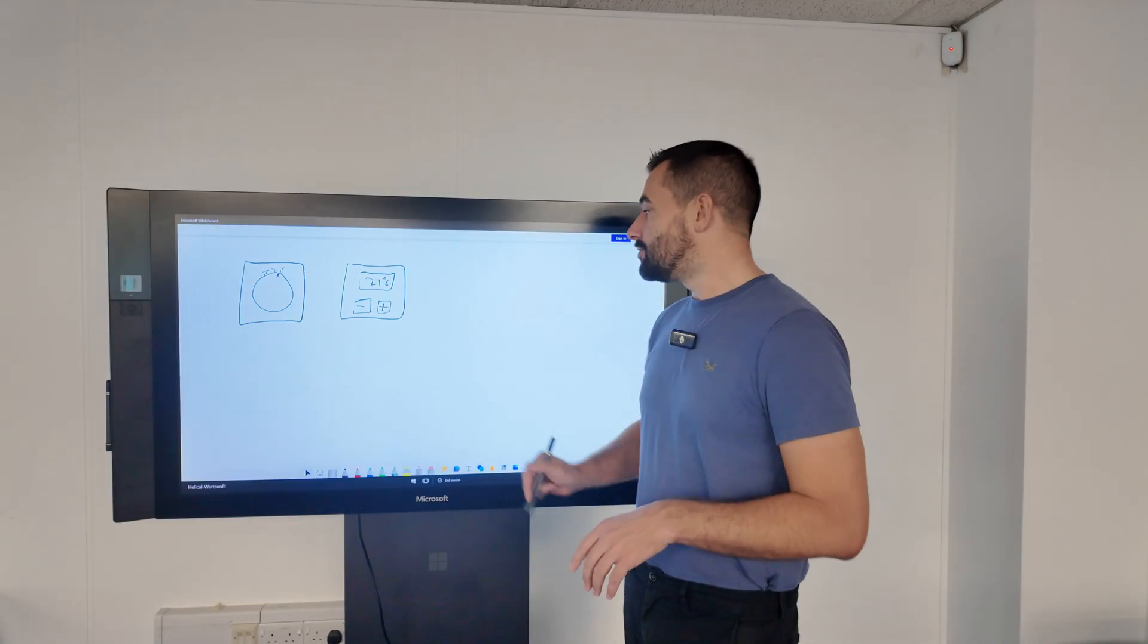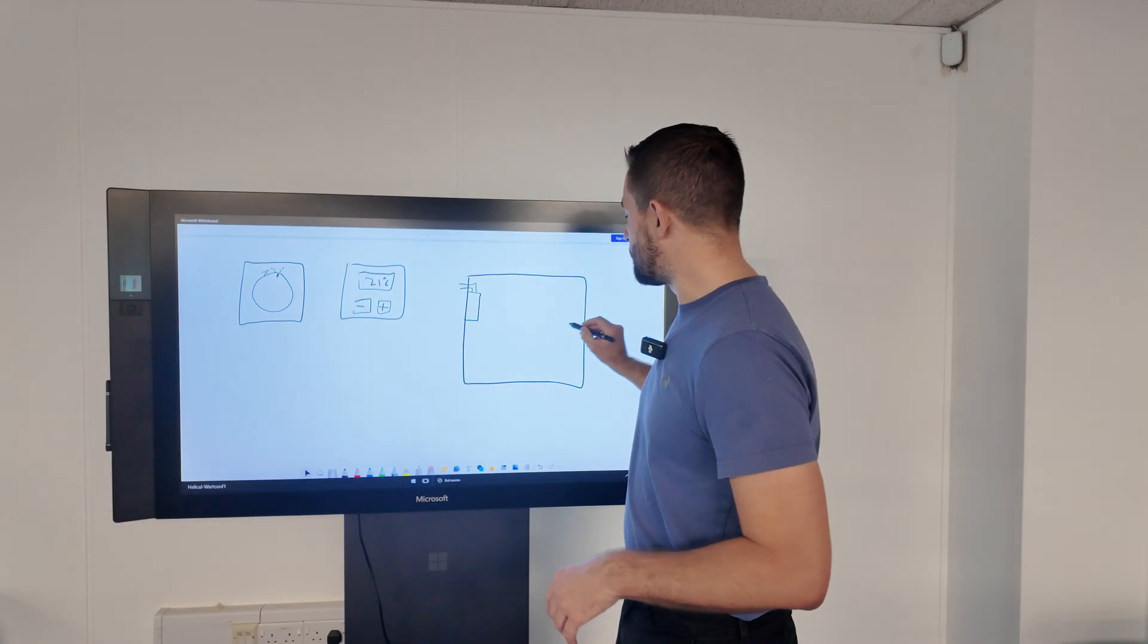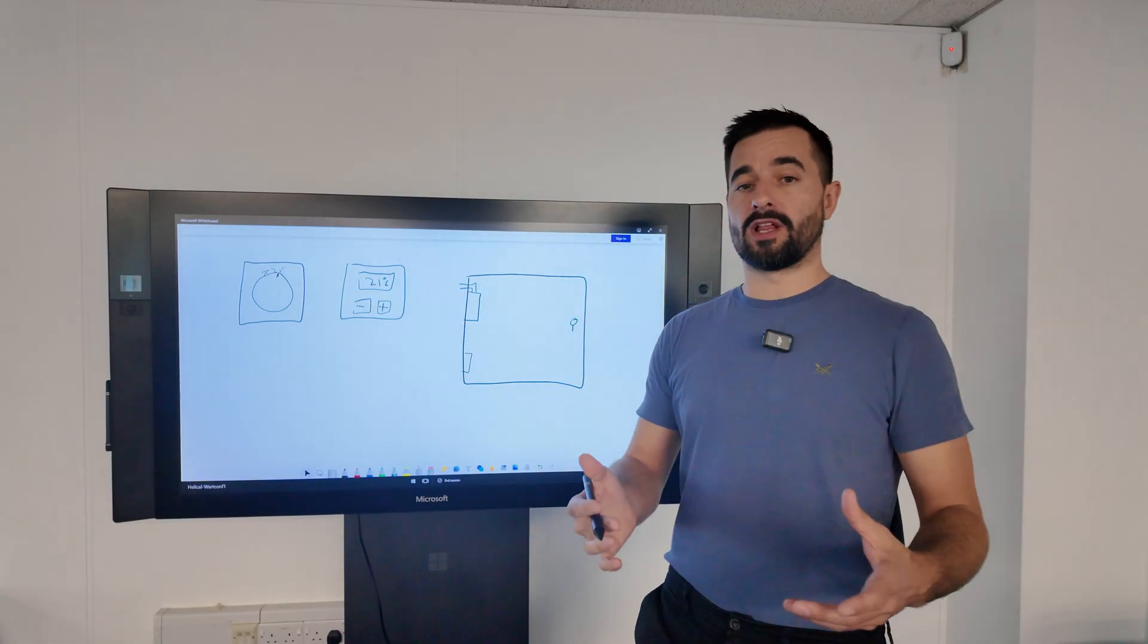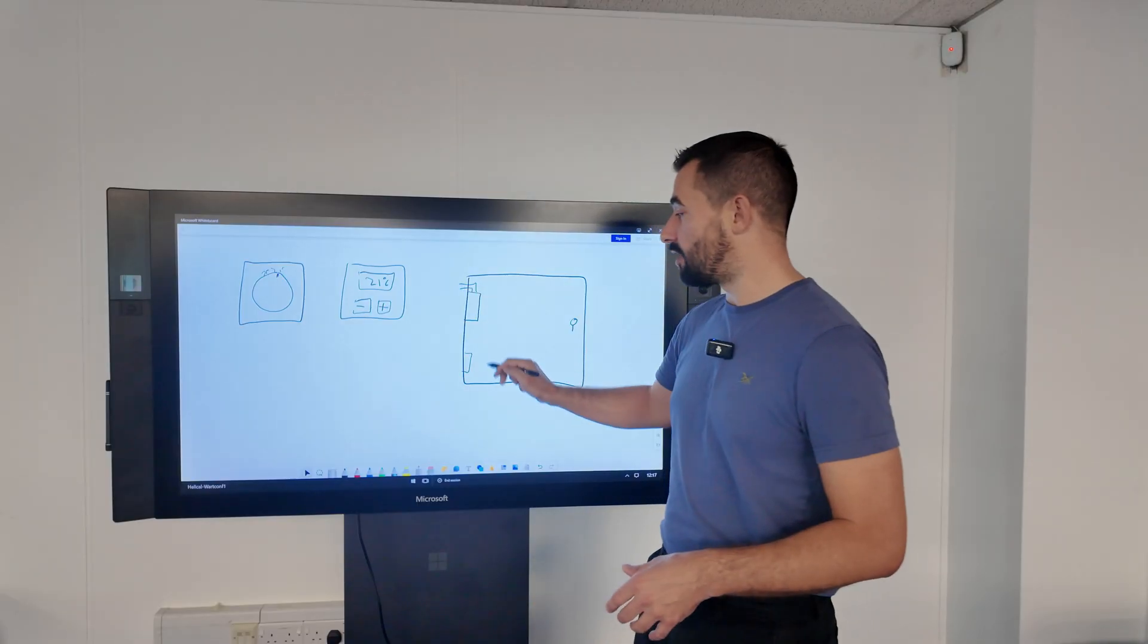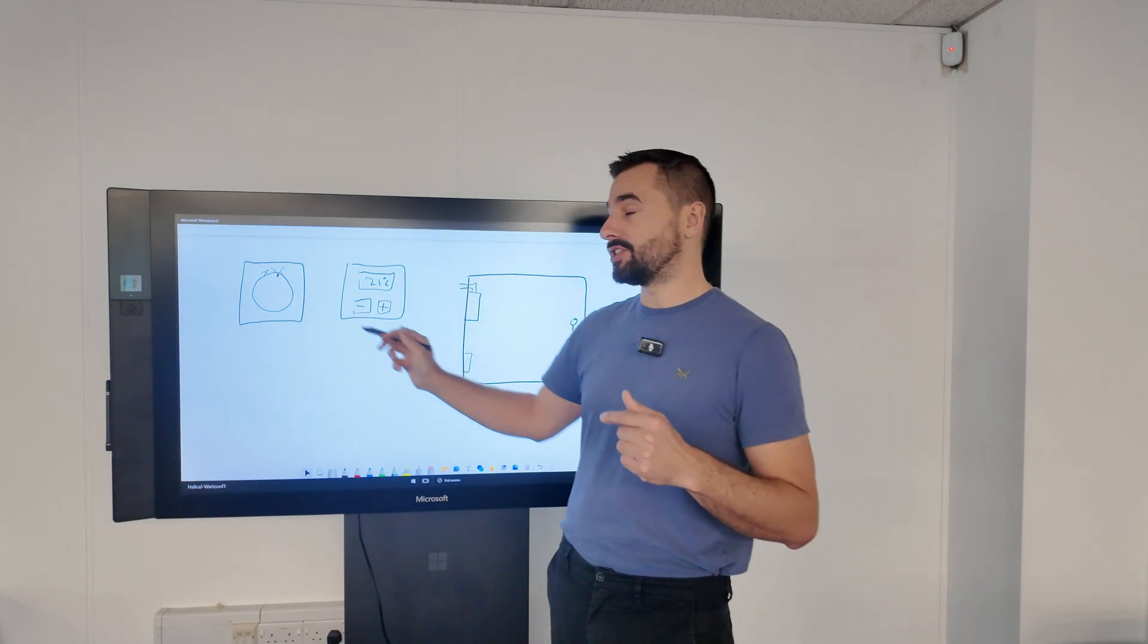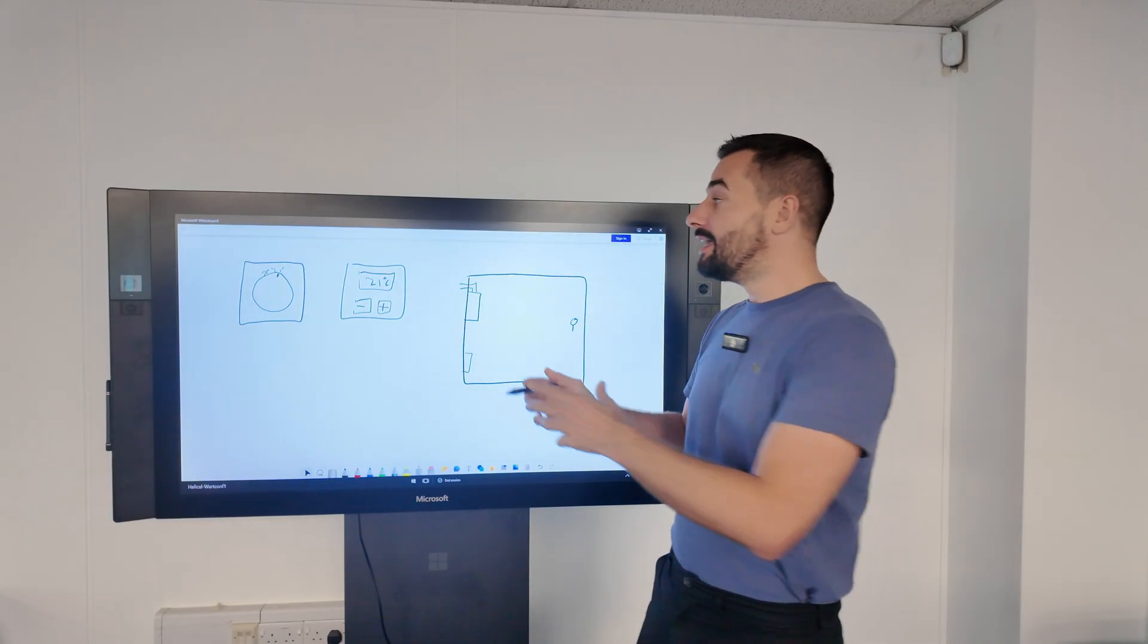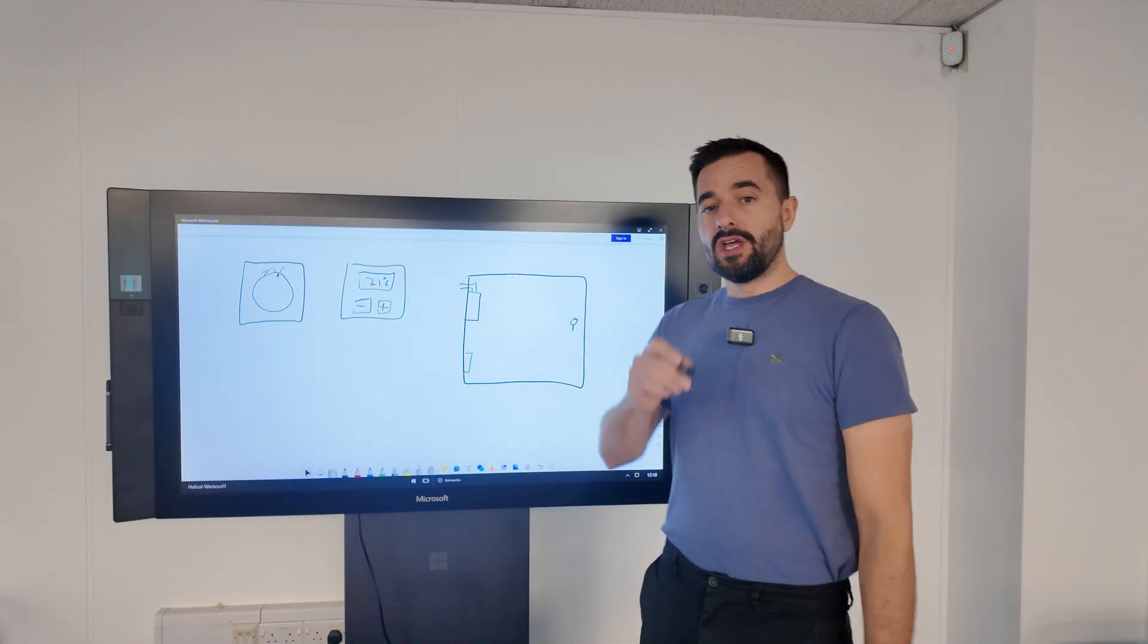You'll have your home, your gas boiler, and your thermostat somewhere in your home. You'll call for heat, that'll turn on, it'll heat your radiators up and your home will get hot. When it reaches temperature these things turn off, turn your gas boiler off. Your radiators start to cool and your room starts to cool. When it drops to that thermostat's differential or hysteresis—what that means is how much it allows the room to drop by before it heats up again—it'll then call for heat again. Your gas boiler will turn on, your radiators will heat up and it'll start to heat your room.